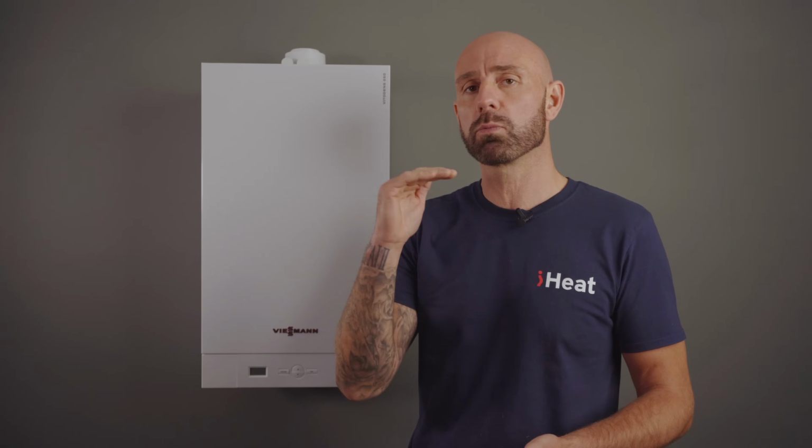If the pressure is too low, then topping up the pressure of your boiler is the first thing to do. If after topping up your pressure you are finding this is dropping again after a couple of days, then this can be an indicator that you have a leak in your system. It is always best to check the pressure of your system when it's cold or the boiler is turned off. When the boiler is on or hot, you can expect the pressure to rise to around 2 bar.